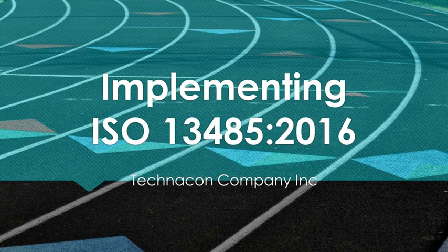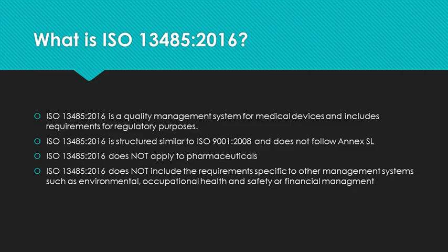with a new set of videos addressing the implementation of ISO 13485-2016. So what is ISO 13485? It is a quality management system for medical devices, including requirements for regulatory purposes. It does not apply to pharmaceuticals. It is structured similar to ISO 9001-2008, the previous edition of ISO 9001, and does not follow the Annex SL.